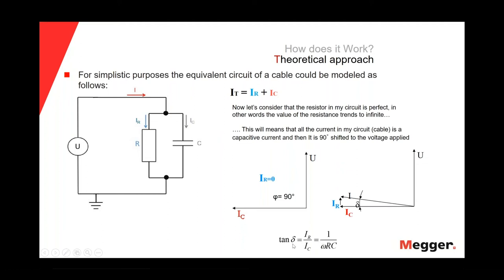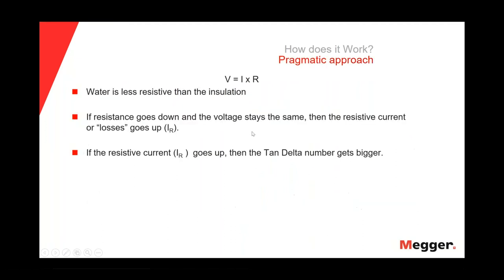And we can see here the function that correlates the resistive current and the capacitive one. This is one approach. There is another easy, pragmatic approach. If we consider the equation that the voltage is equal to the current multiplied by the resistance, and if we consider that the water is less resistive than the insulation, that means the resistance will go down, and if the resistance goes down and the voltage stays the same, then the resistive current, or losses, goes up. And if the resistive current goes up, then the tan delta number gets bigger.